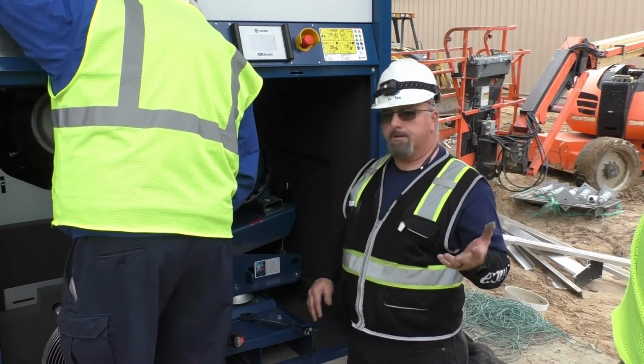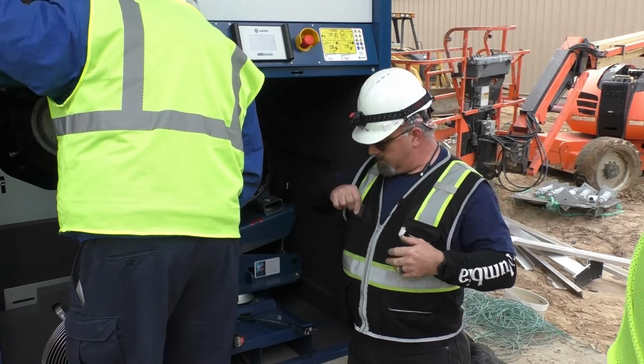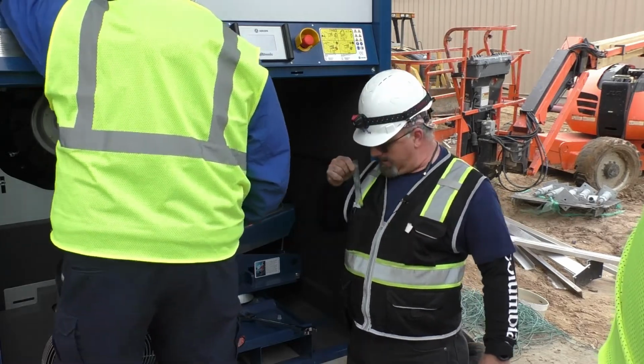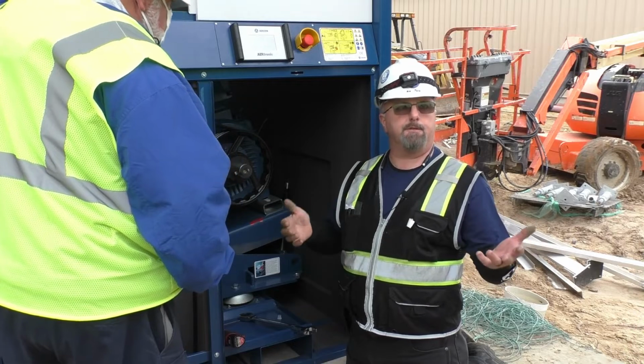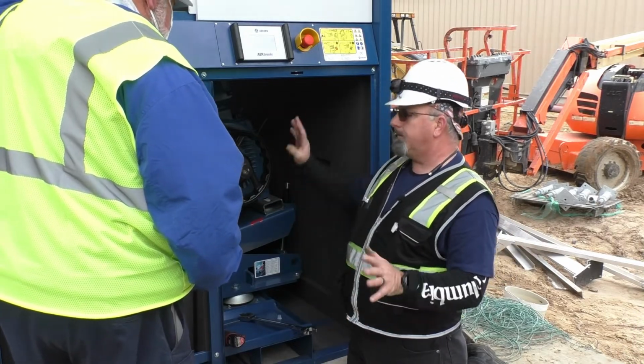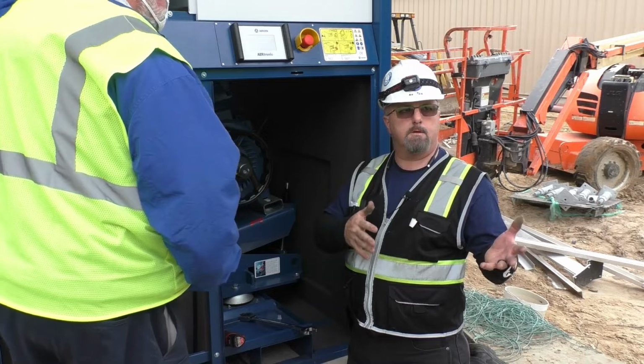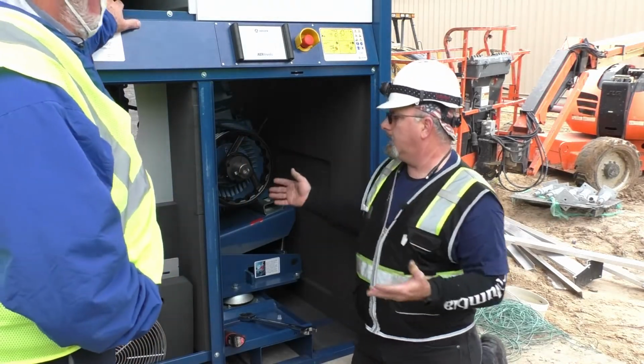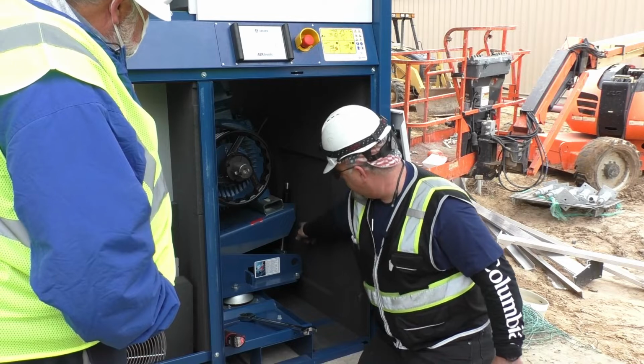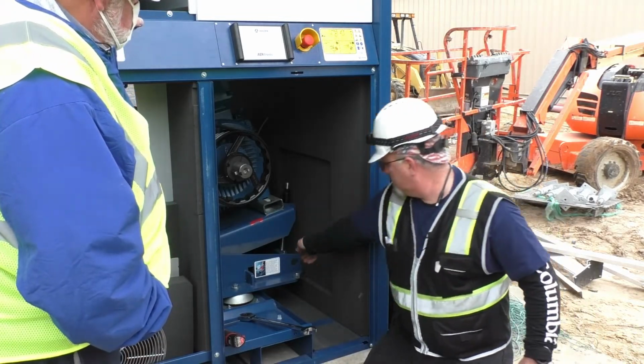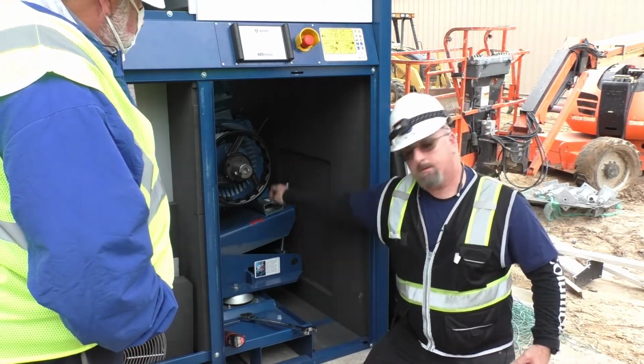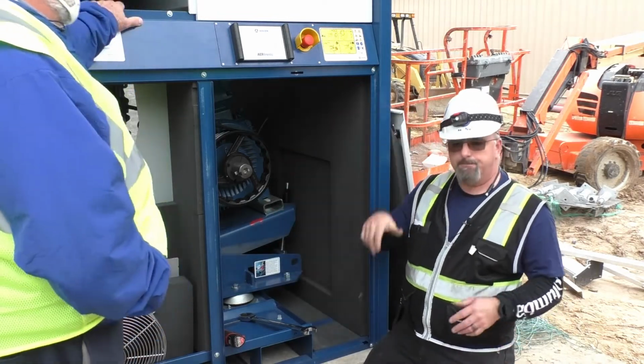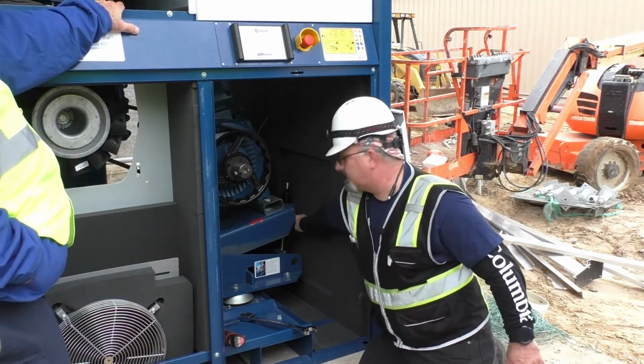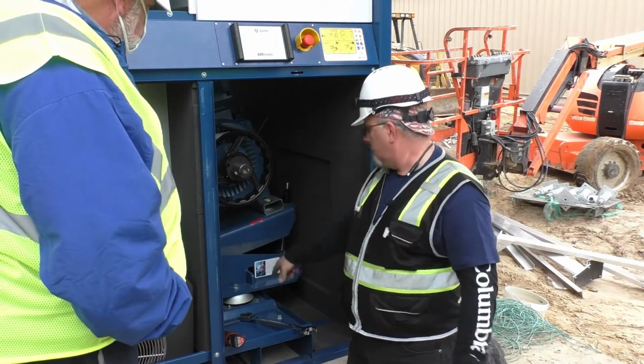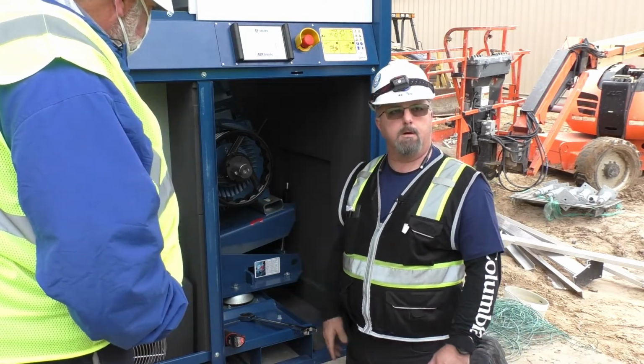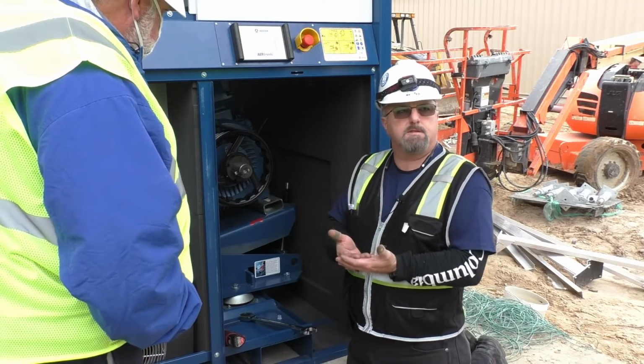Now, rule of thumb, you may not carry a little handy dandy ruler like I have when I'm doing startups, because usually the first time when I close the unit up and I put the belts on, I set it to that interval. So that way when you go back to do the service, all you have to do is break loose that bottom jam nut, and then I have this top jam nut that'll be on top of it. You'll back that off and you'll raise your piece up against this, raise your motor, change your belts. You never have to really do anything but break that bottom one loose. It stays in place once it's set.